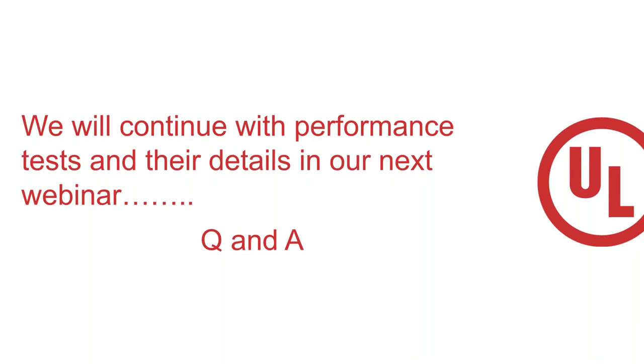Yeah, it's a very good question. Basically, as I mentioned in the presentation, it depends on how big the family is. So now you understand, all my viewers have understood this. Depending upon the family size, my testing also increases. But normally, within 7 working days, we can complete all the testing except short circuit at the Abu Dhabi lab. Short circuit for one MDB, main distribution board, or SMDB takes 2 days. Roughly around 10 days, we can complete all the testing for one MDB or one switchboard as per IEC 61439-1 and 2, and within another 7 working days we can release our certificates and reports from the UL side.